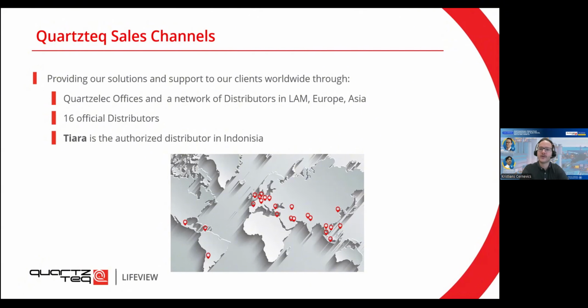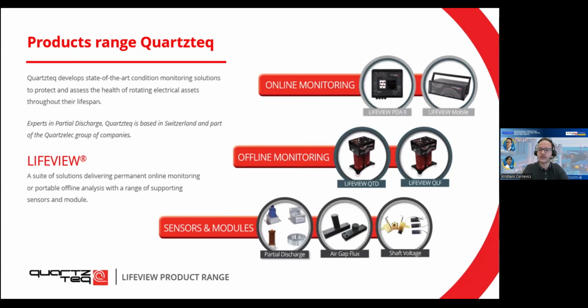And just to give you a very quick overview of the type of products Quartzteq offers in the very beginning, and then I'm going to go into more detail to explain why to use a specific type of product, what are the advantages, disadvantages. So essentially, we're developing condition monitoring solutions to protect and assess the health of your rotating machines. Mainly, we're specialized in partial discharges, but also in shaft voltage measurements and air gap flux measurements. We offer both online and offline monitoring solutions. So depending on your needs, on the accessibility of the machine, on the schedule of the shutdowns, we can find different solutions. And we also offer sensors and modules that are capturing this data.